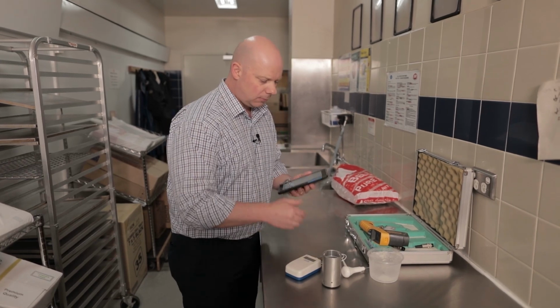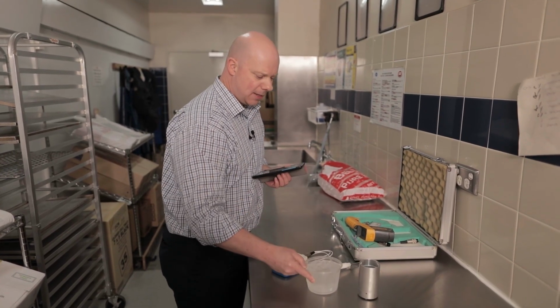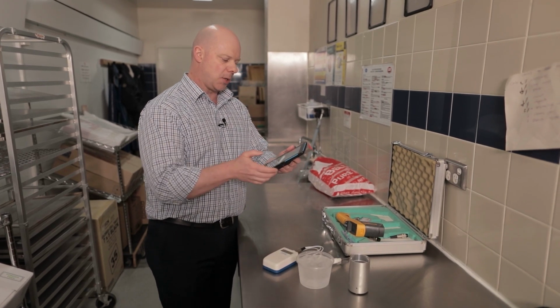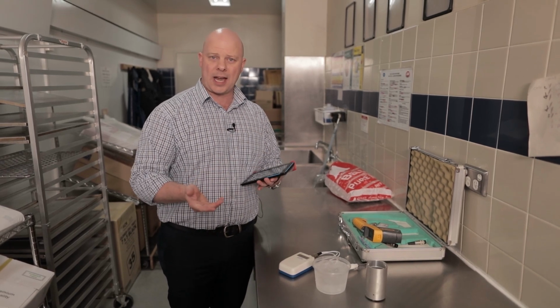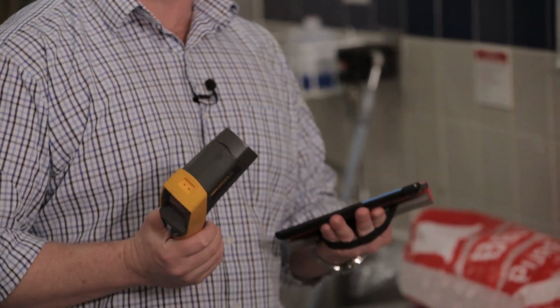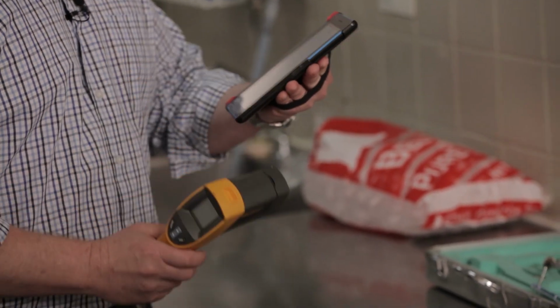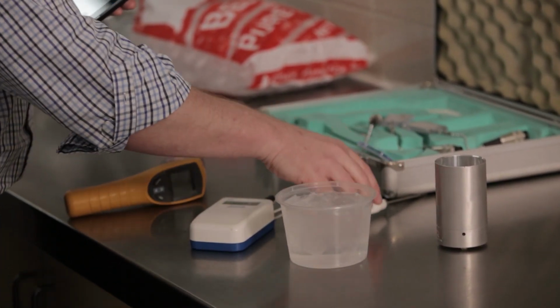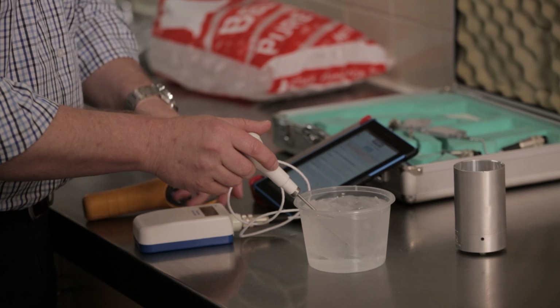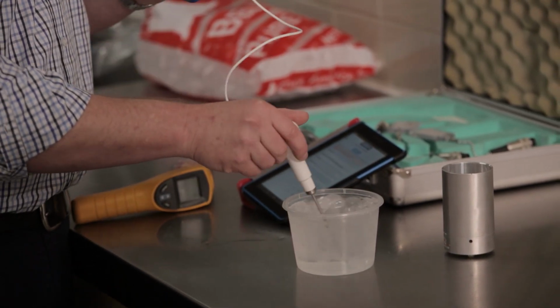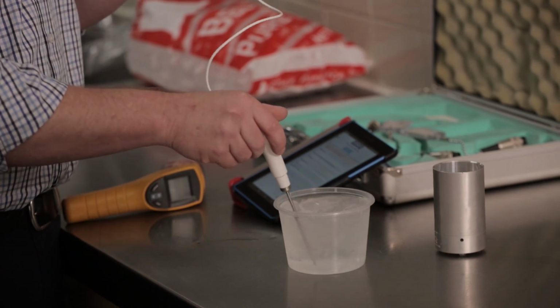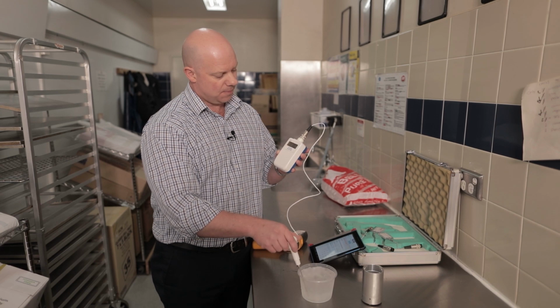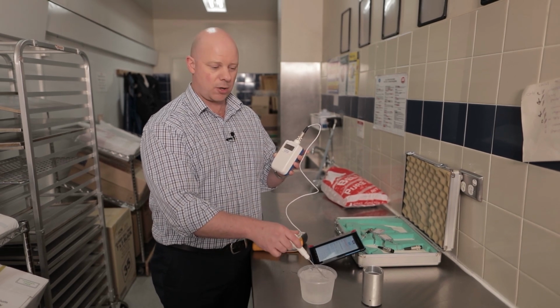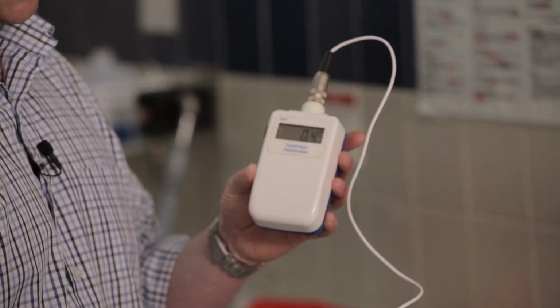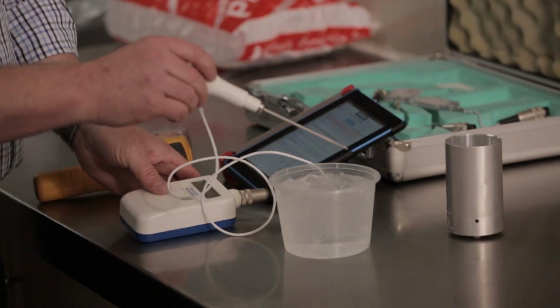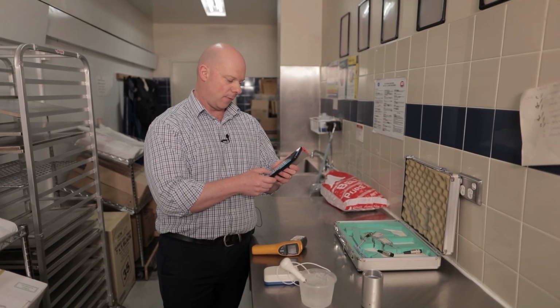Again, with this check, we've got our ice water, which we've already pre-prepared. We've chosen that we're going to do our temperature probe comparator IR temperature gun, because we want to check the accuracy of this gun, and we've established that the only way we can do that is if we use a comparator pot. So we've chosen that. What we want to do is we want to use the ice water again. We want to make sure our digital thermometer is turned on. I'm going to leave that there. We're just going to circulate that water, and we're going to wait for this to hopefully come back below 1 degree, remembering that that needs to be within plus or minus 1 degree of 0. And we can see that we're still sitting at 0.4 degrees. Once we know that, we've tested the accuracy there, you put in your system 0.4 degrees.